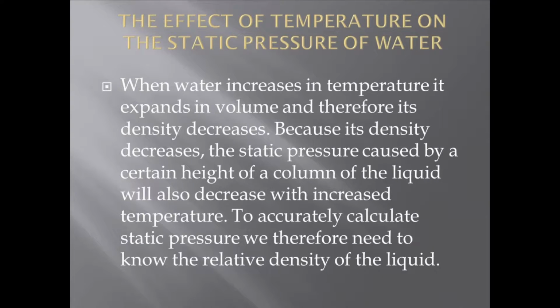The effect of temperature on the static pressure of water. When water increases in temperature, it expands in volume and therefore its density decreases. Because its density decreases, the static pressure caused by a certain height of a column of liquid will also decrease with increased temperature. To accurately calculate static pressure, we therefore need to know the relative density of the liquid.